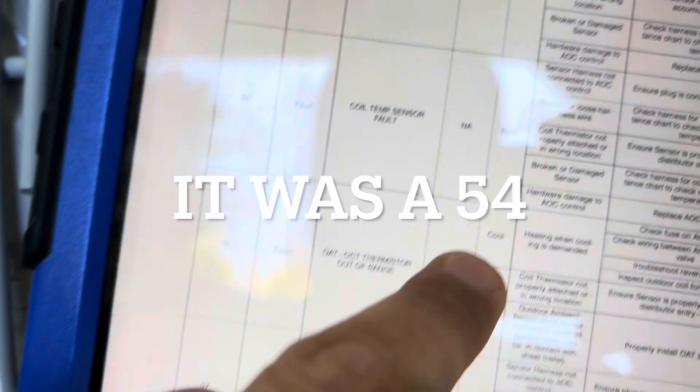We also had a 54, which is what it's locked out in now - suction temp sensor fault. Possible causes include sensor harness not connected, suction thermistor not properly attached, broken or damaged sensor, or hardware too damaged.